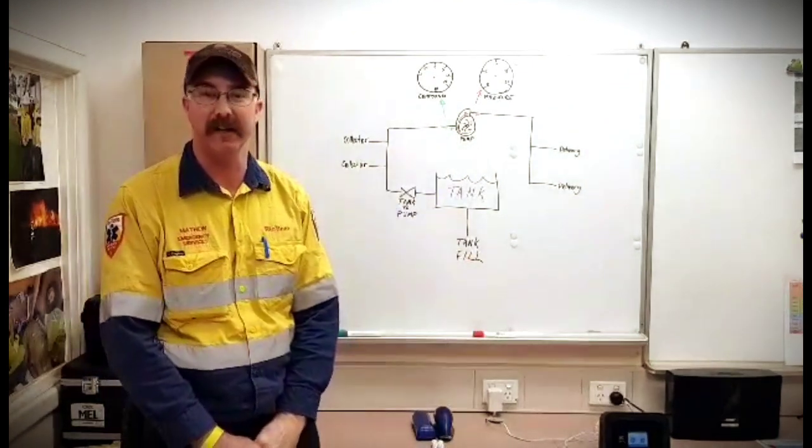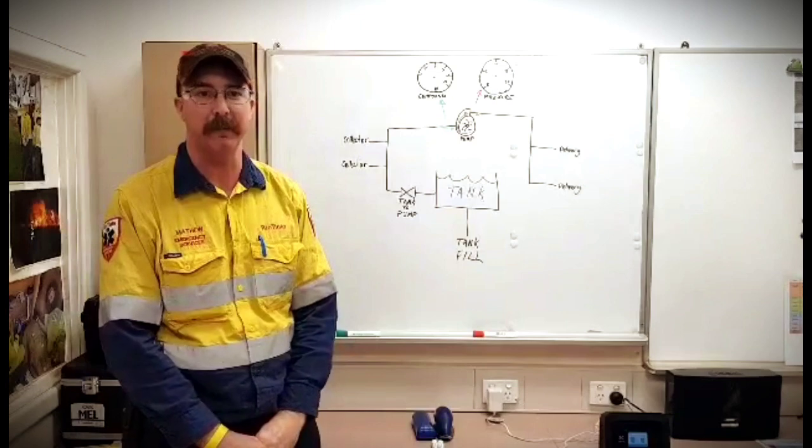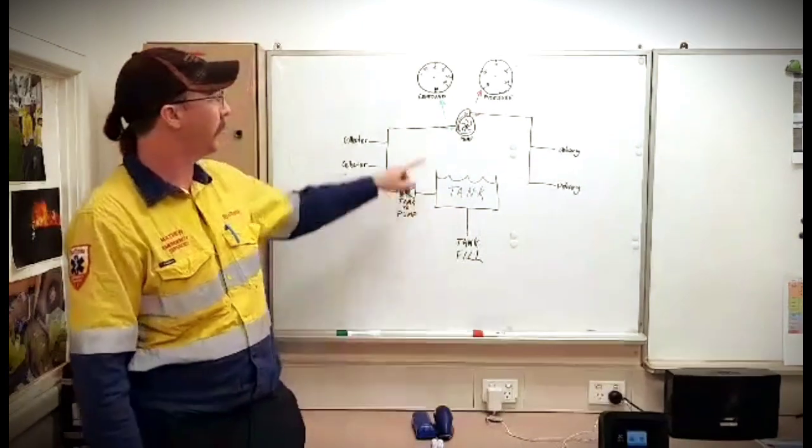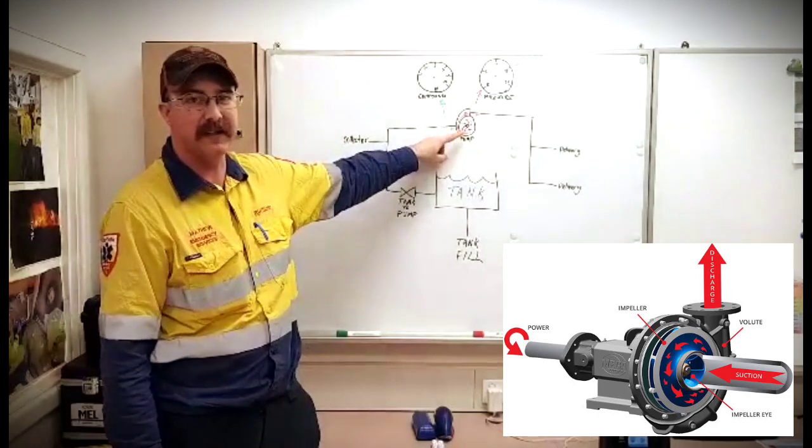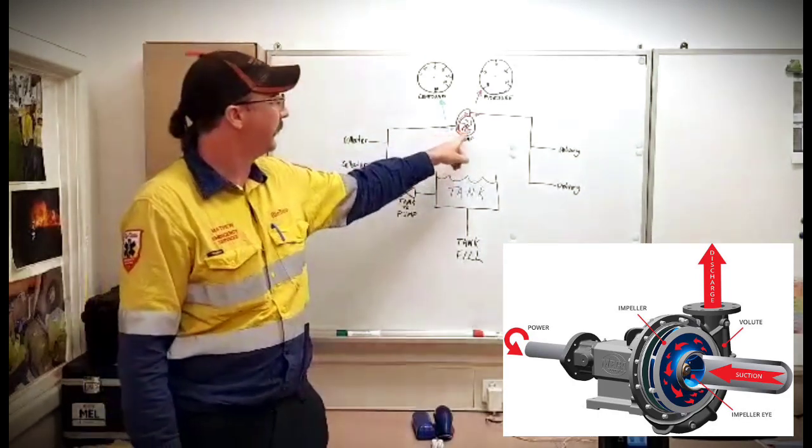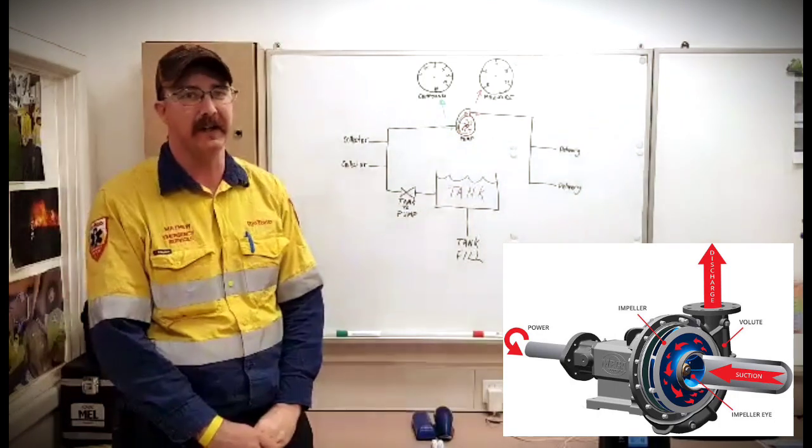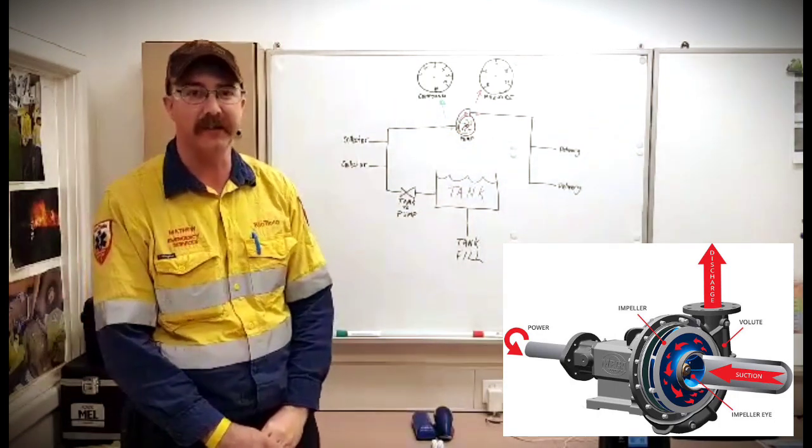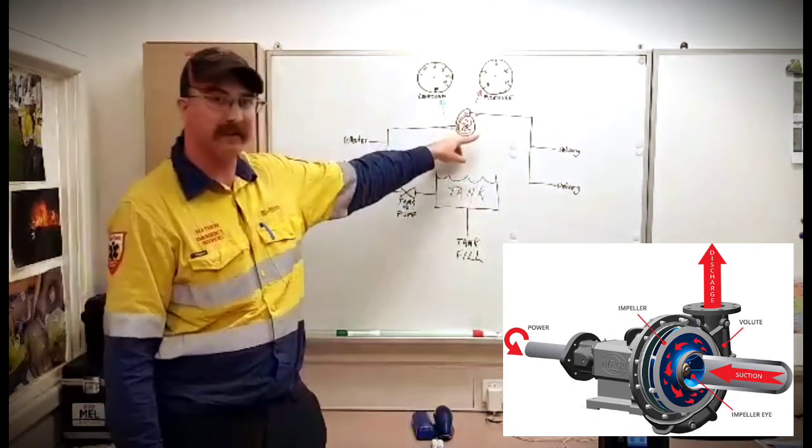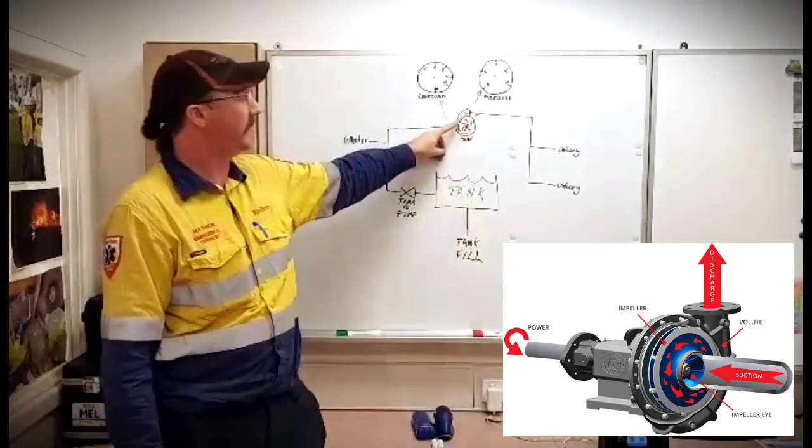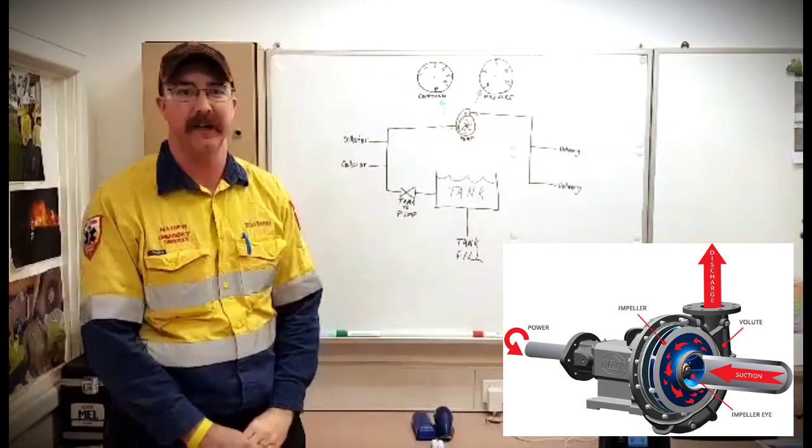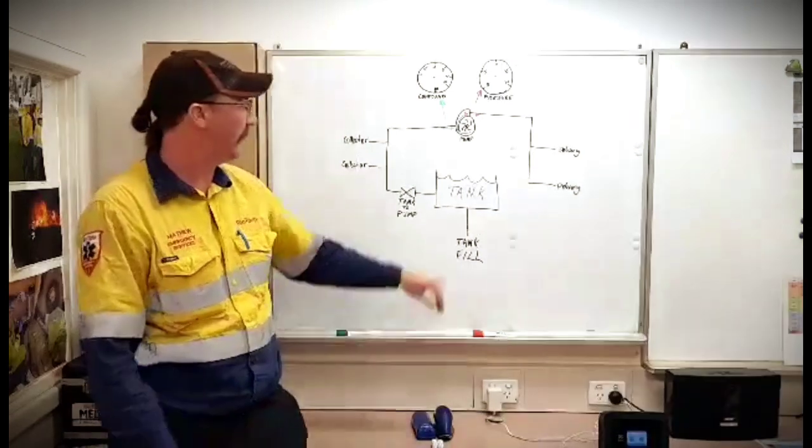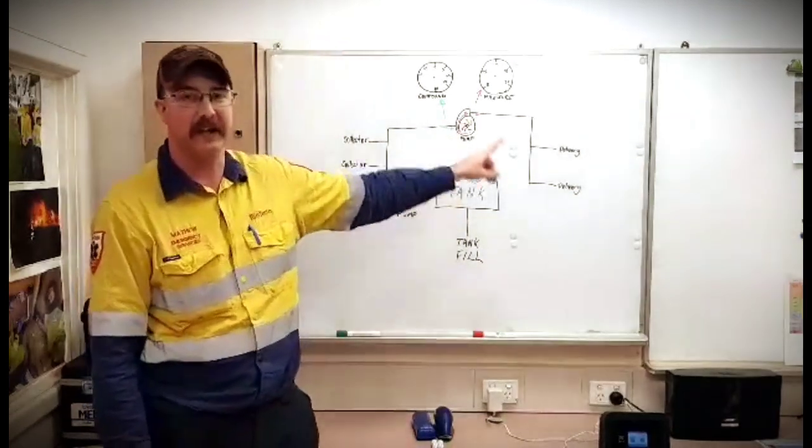Now in the fire service we use a centrifugal pump. The way this works is the water comes in through the eye of the pump which is in the centre here, and it travels through the vanes of the centrifuge. Here's the outer casing of the pump. It's released in here which we call the volute and then out the outlet. This takes it from a static supply from our tank into an energized supply.